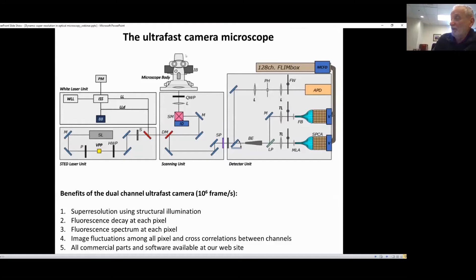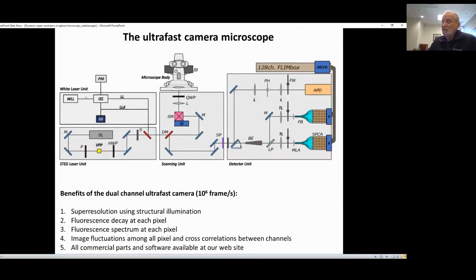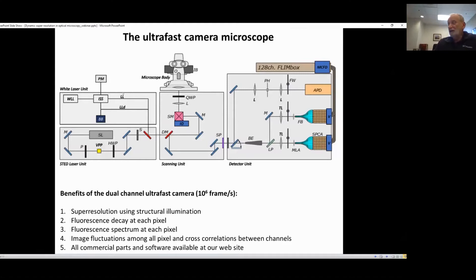You start from a laser, and we use a white laser unit. The white laser unit produces pulses of light which are about ten picoseconds — not femtoseconds, so you cannot do two-photon excitation. The light then goes into the STED unit, which is very important because it will give us the super-resolution based on the STED principle. Once the light has either passed through the STED unit or not, it goes to the microscope, which has a scanner to acquire the image. The fluorescence light from the microscope goes through the detector we call the VESPA, because if you look at them, they look like the eyes of a big bee.